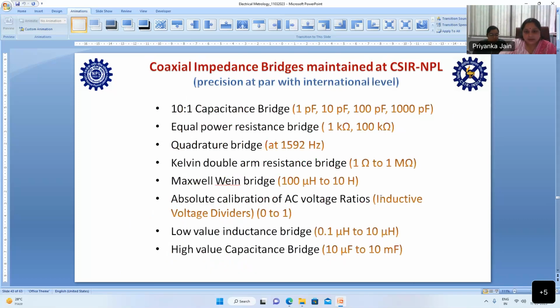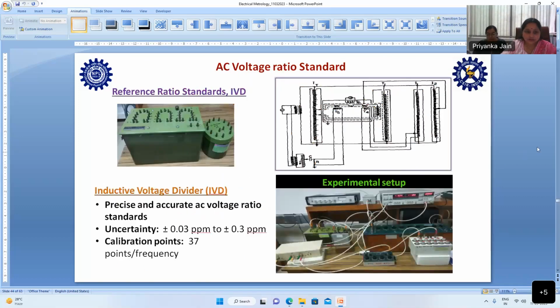And these are the list of bridges which we are maintaining to disseminate the traceability to the industry and our customers. So we have the 10-1 capacitance bridge, equal power resistance bridge, quadrature bridge, Kelvin double arm bridge, Maxwell-Wien bridge, absolute calibration of AC voltage ratio, low value inductance bridge, and high value capacitance bridge. Ranges are already mentioned in the previous traceability chart.